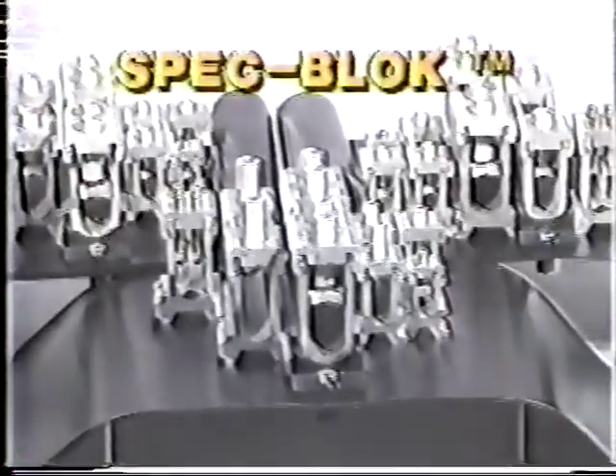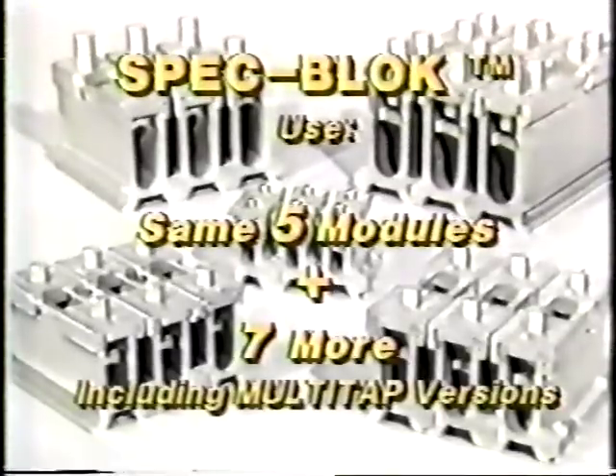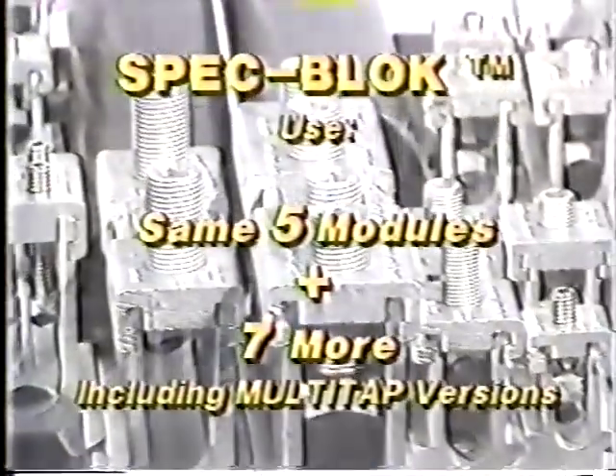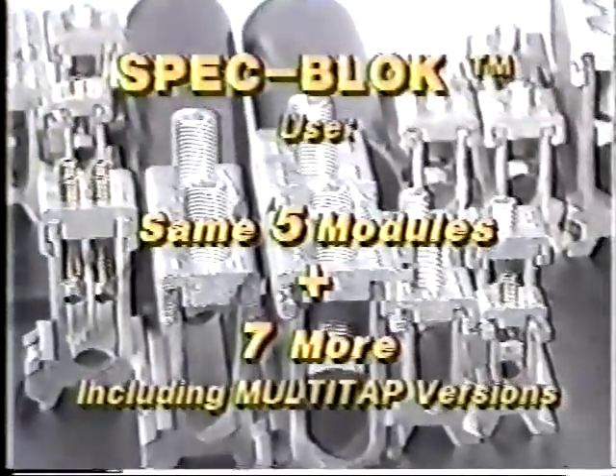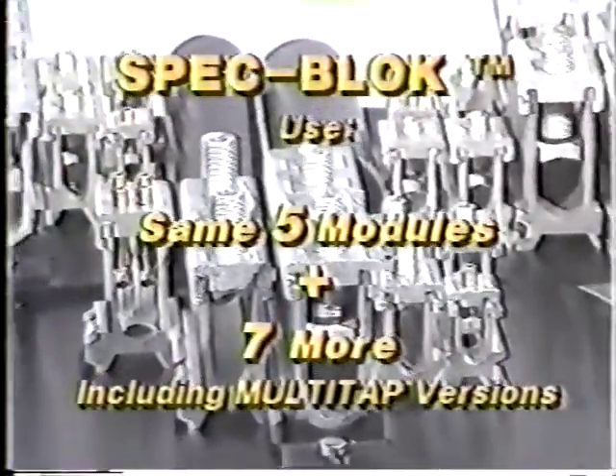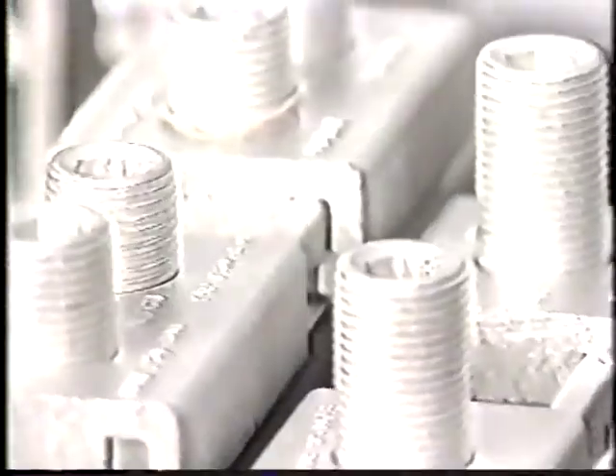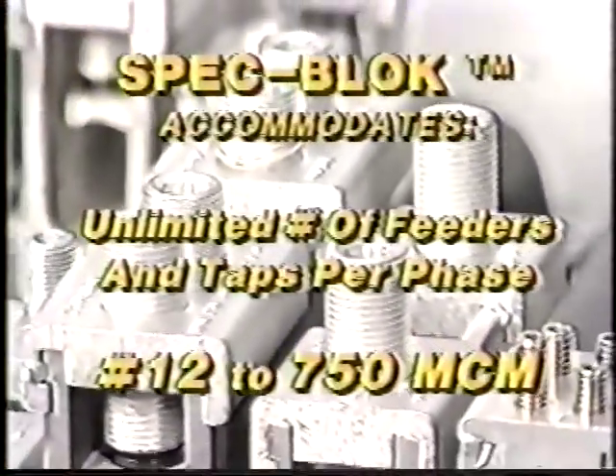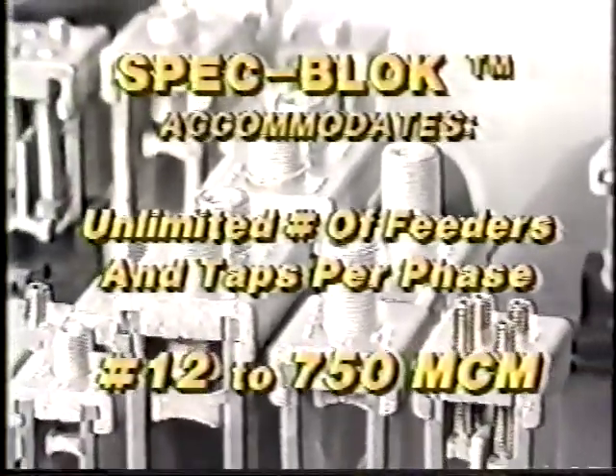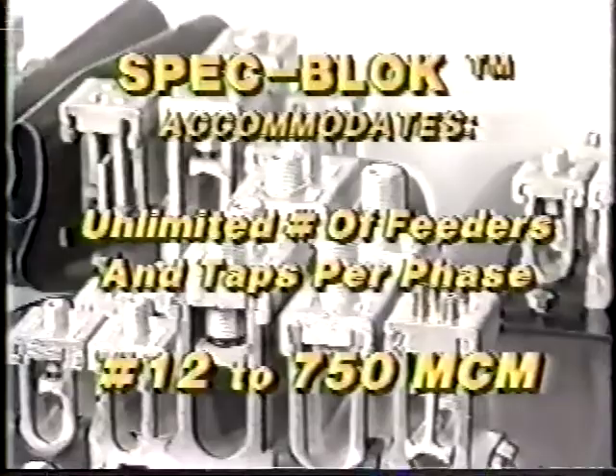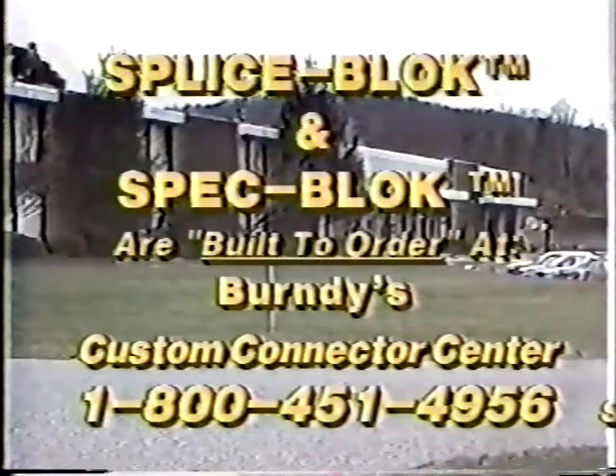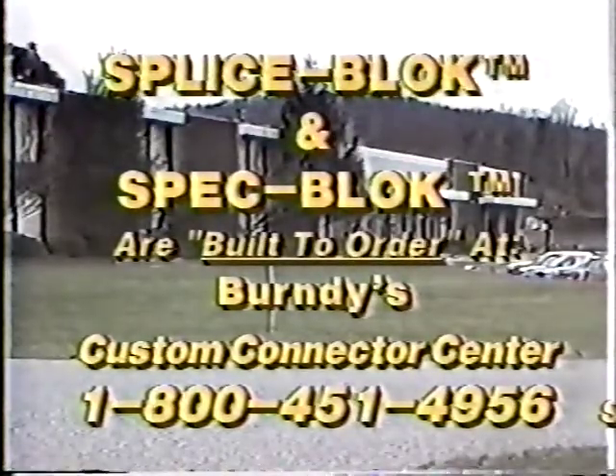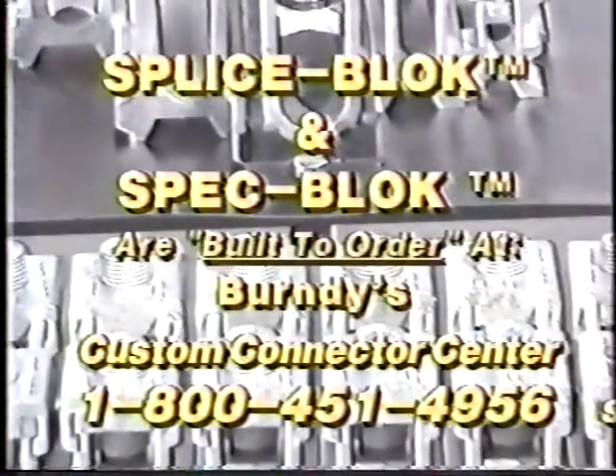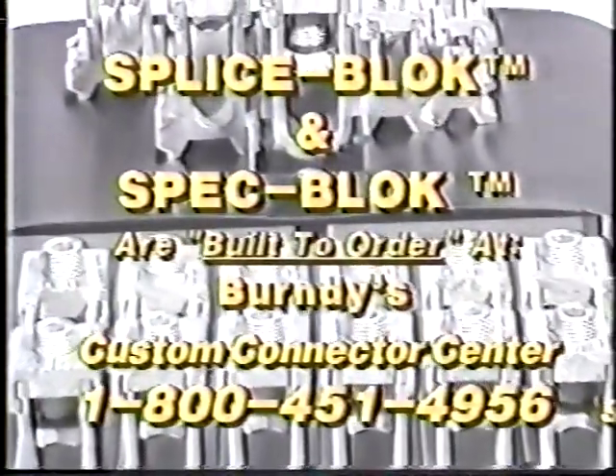Spec block assemblies use the same 5 modules as our splice block line, plus 7 additional modules, including multi-tap configurations. With these components, Burndy can provide assemblies to accommodate unlimited combinations of feeders and taps per phase, ranging from number 12 to 750 MCM conductors. Due to their custom nature, Burndy splice blocks and spec blocks are permanently assembled to order at our Custom Connector Center. Because they are assembled from modular components, we can provide a fast turnaround to meet your requirement.